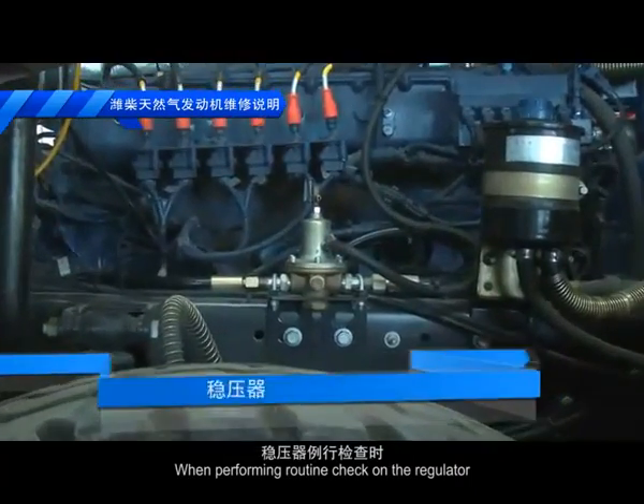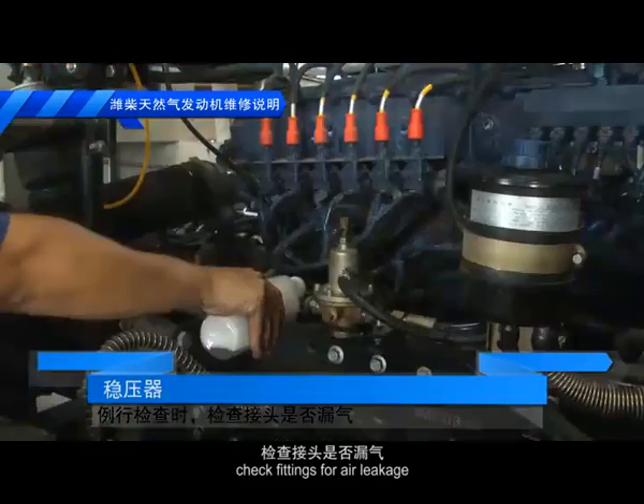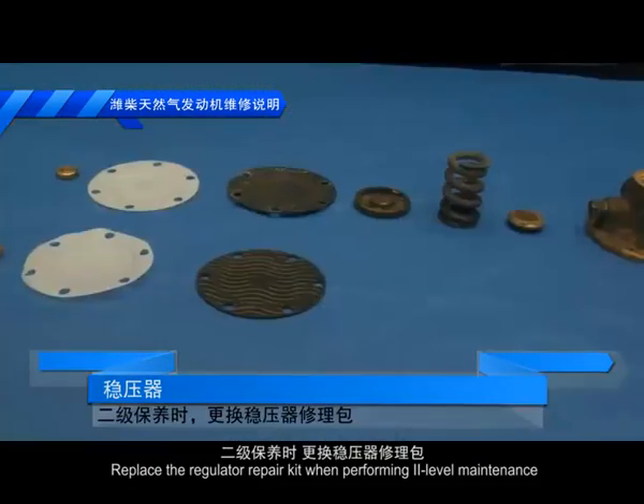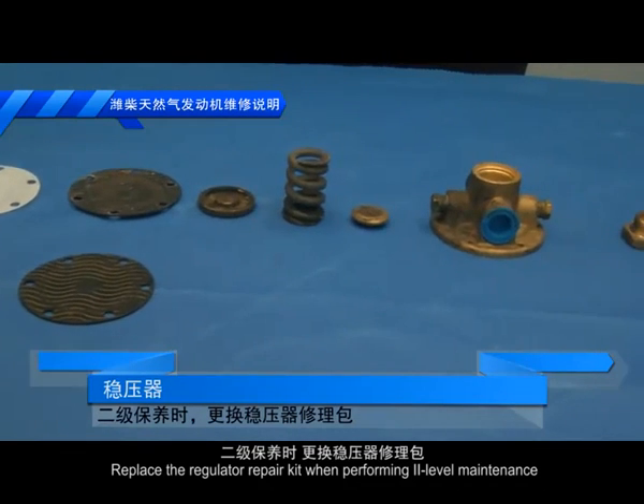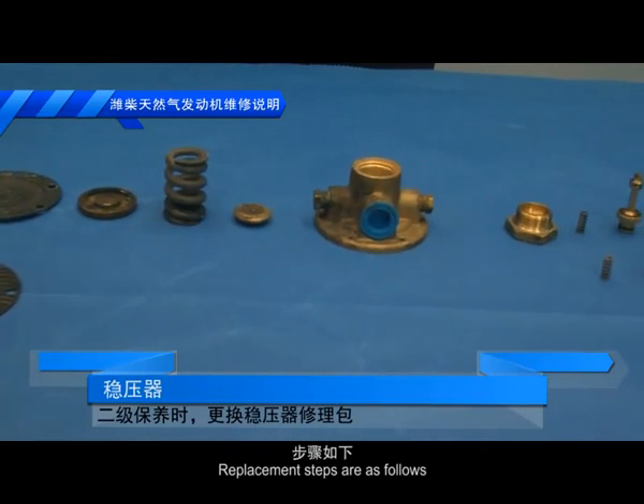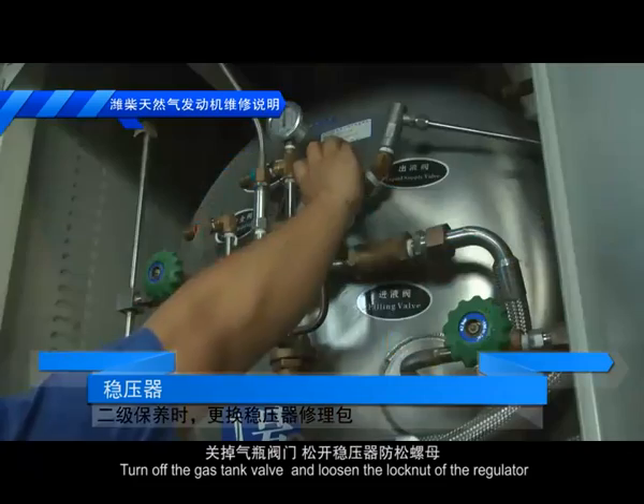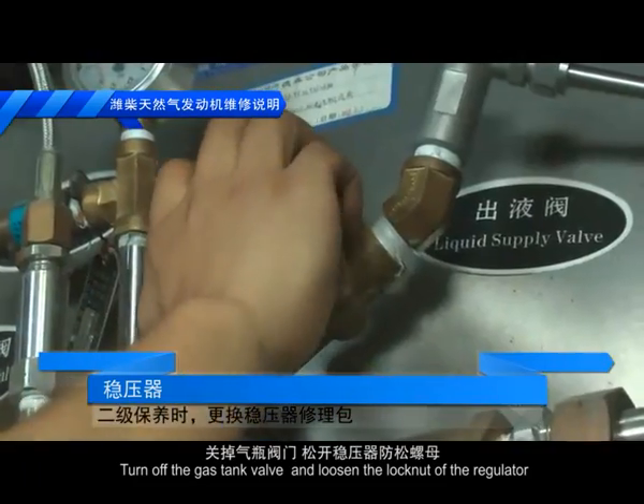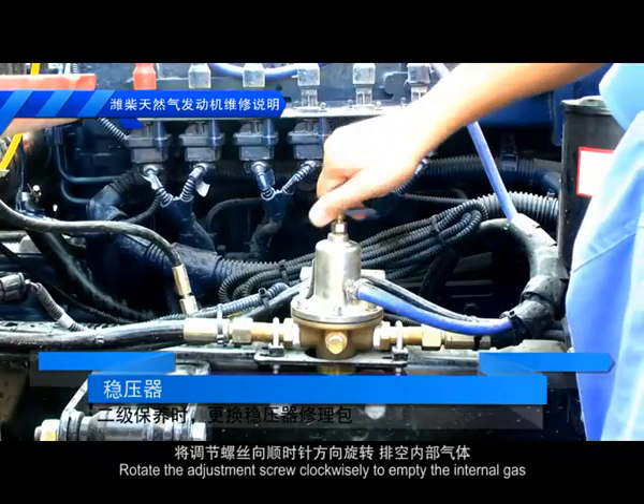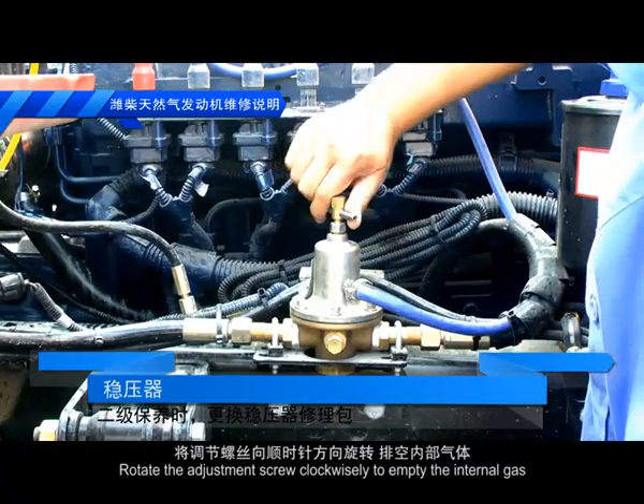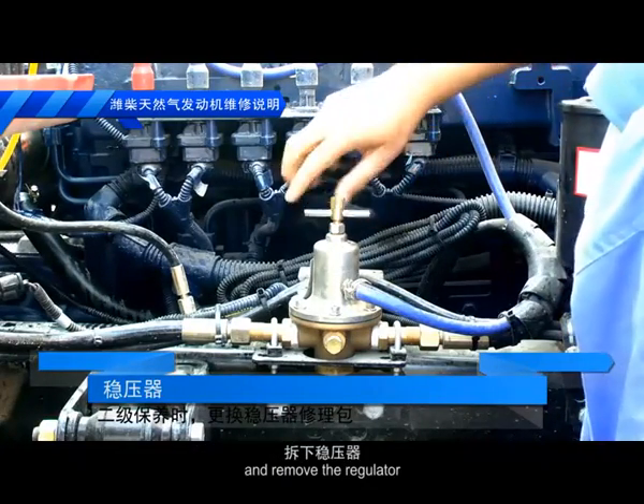When performing routine check on the regulator, check fittings for air leakage. Replace the regulator repair kit when performing two-level maintenance. Replacement steps are as follows. Turn off the gas tank valve and loosen the lock nut of the regulator. Rotate the adjustment screw clockwise to empty the internal gas and remove the regulator.